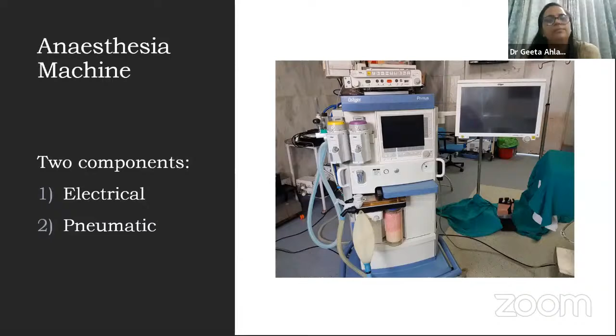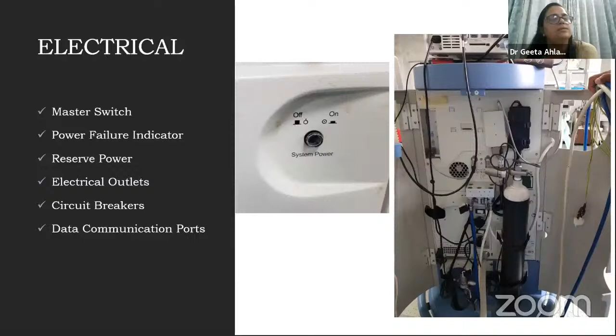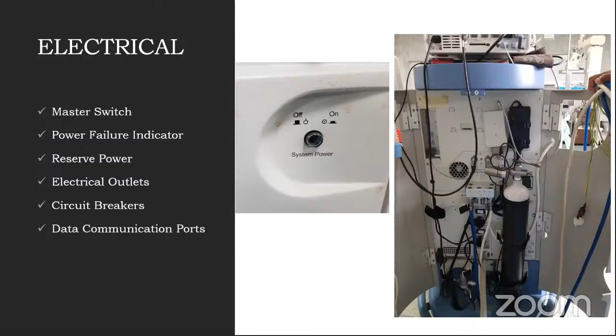Whether it is a pneumatic machine or an electrically driven machine, all necessary checklists are as important as the machine itself. Let us talk about the electrical part first. We are all sure of the master switch, which keeps our machine on. Power failure indicators are equally important because now we are depending on the power. So we should also have a reserve power like a battery. The electrical outlet should be checked before you check the machine. All circuit breakers should be in place before you switch on the machine. And now in this era, the data communication ports are equally important.